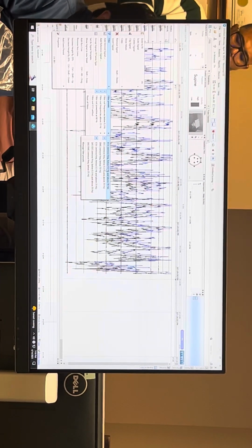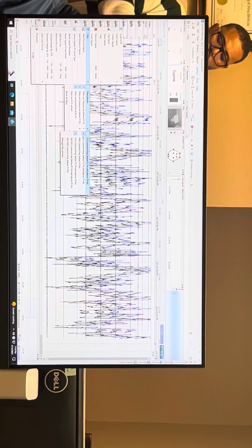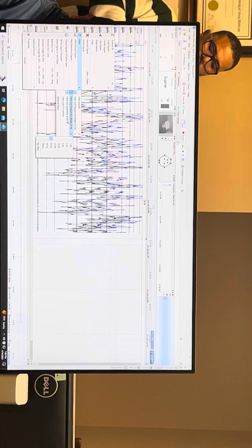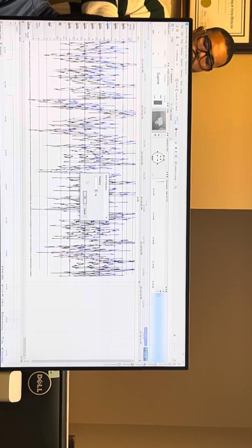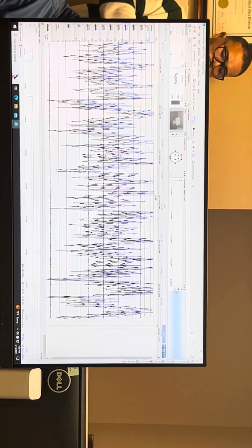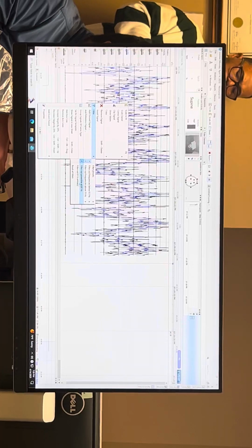Under filters, we have preset filters for EEG, EOG, or EMG. These are straight out of the AASM manual, what they're supposed to be. If you need to tweak things from there, you can adjust your filter out above, filter out below. And if you don't see the number that you're looking for here, you can hit other, and you can type in whatever value you want to put in for the filter. The other cool thing in filters, most of these will have your notch already added on it, your 60 hertz. But we also have this filter out ECG artifact.